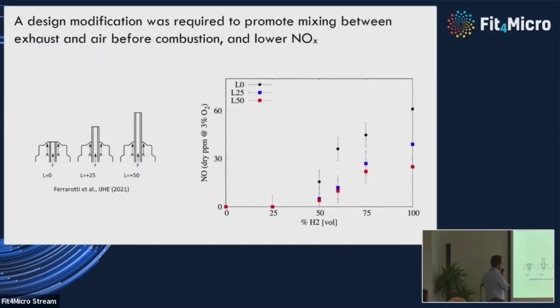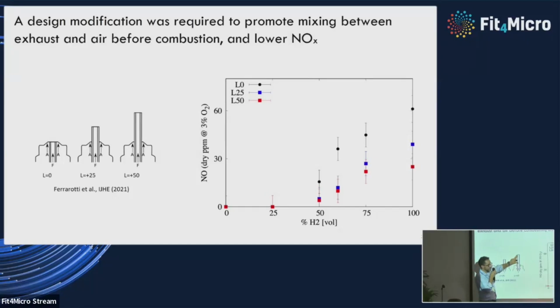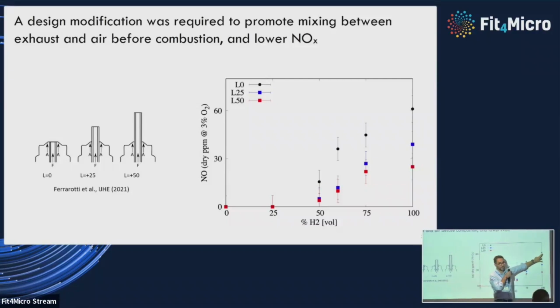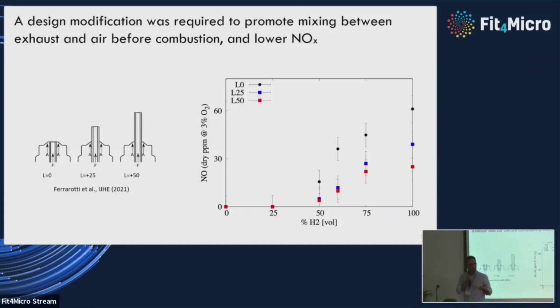And so what we did was to say, okay, let's think about how we can still make the process slower, in the sense to make the two processes competitive with respect to each other. So if we design a new injector for the fuel, we can actively delay the time or the location where the fresh reactants will meet with the exhaust gases and react, right? So we designed an injection lance for the fuel that is 50 millimeters longer. And you see that by doing this, you actually halve your NOx, going from 60 to 30. So still you don't have the single digit, but you can reduce from 200 to almost 30 ppm, which is a big step. So I think this demonstrates clearly that flameless is not an absolute concept. It's not a universal concept.